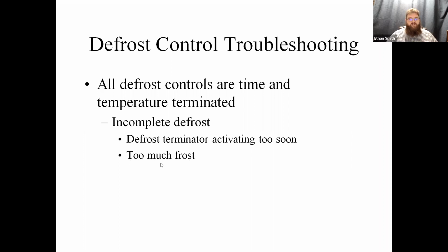So if there's just too much frost buildup, it can't defrost it. So that would be a component of not having set the termination temperature properly. Undersized heat pumps tend to suffer from this quite a bit. They have excessively long heating cycles, and so we may run into a situation where these things are running nonstop and they're simply not able to keep up, and so they tend to accumulate frost more readily than others.